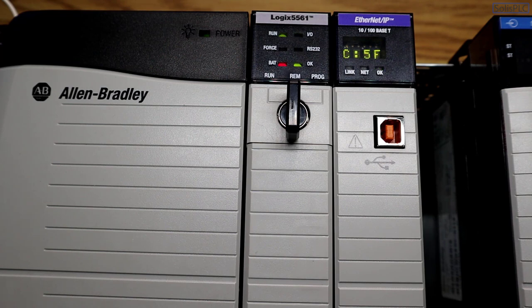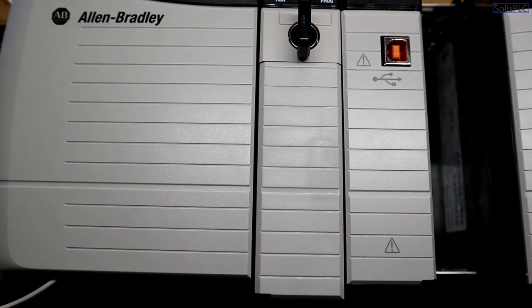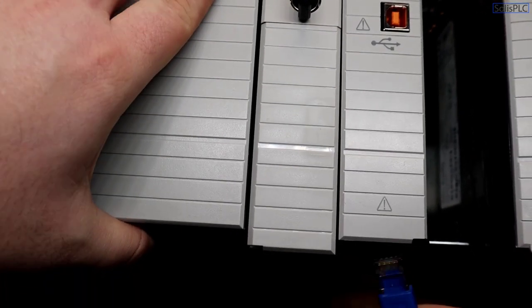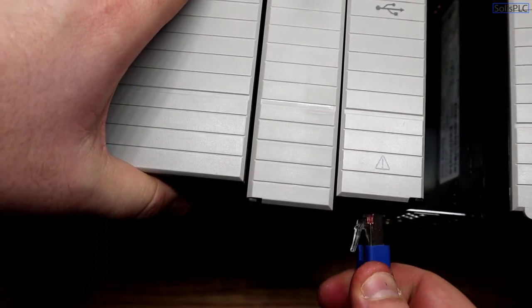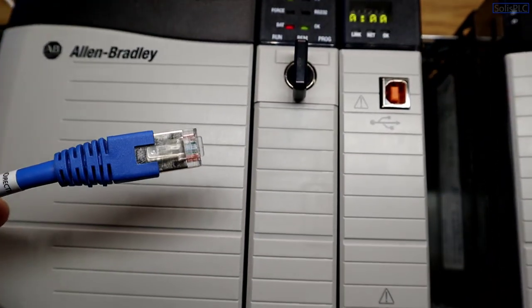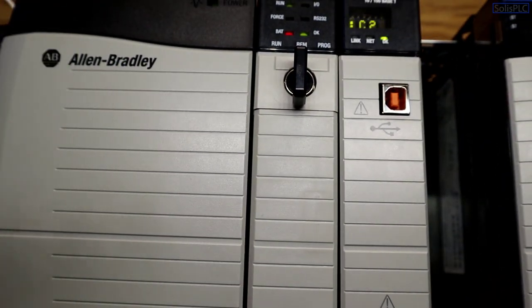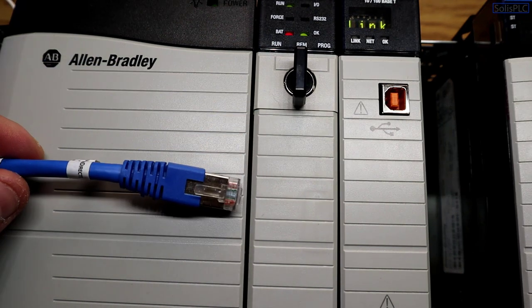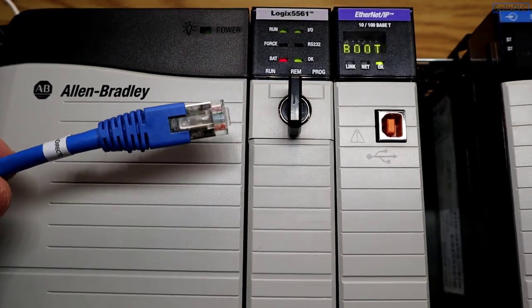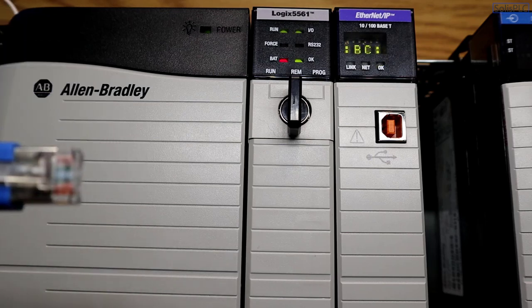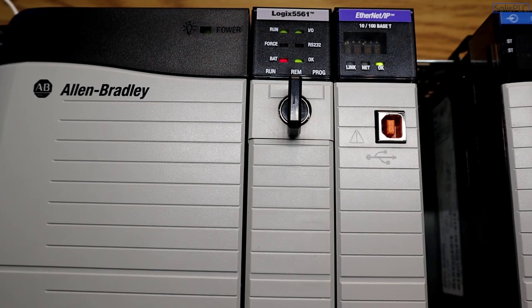So what we're going to do next is I'm going to take my Ethernet cable, which I showed to you, which you've seen many, many times. And I'm going to plug this in at the bottom of the card. And the other end is going to go directly into my laptop. I do recommend that whenever you're setting IPs on your devices, you plug in a single device just to avoid some mismatches, or if you have other devices talking, it might be a little bit difficult if you're going through switches. I do recommend that you connect directly to your devices when you're setting IP addresses. So let's transition to BOOTP right now.